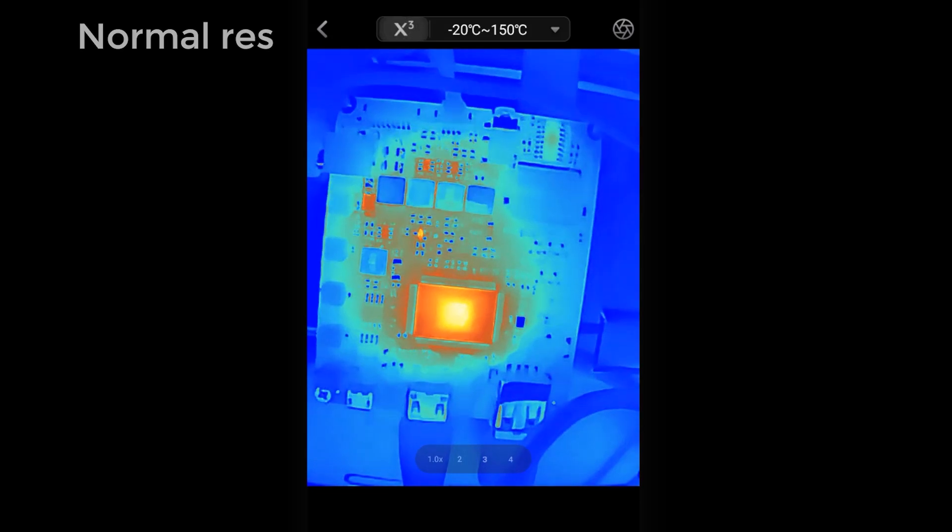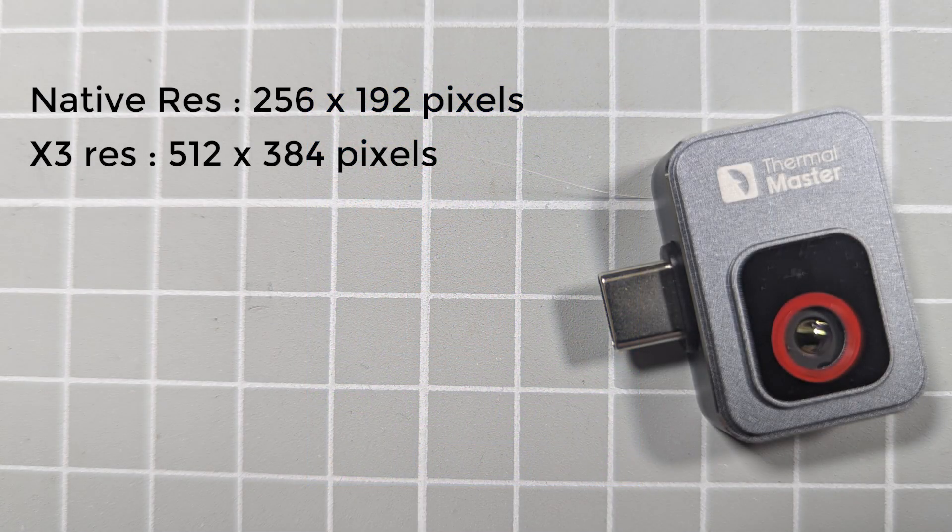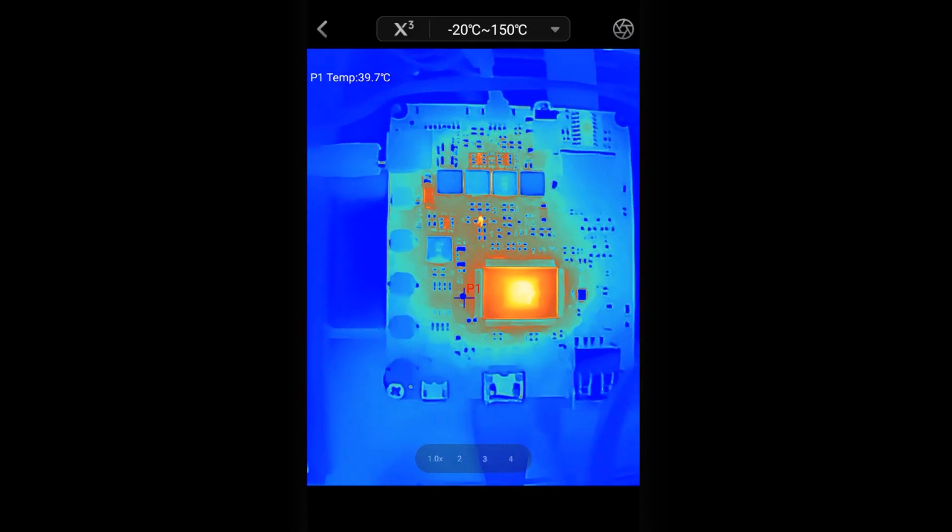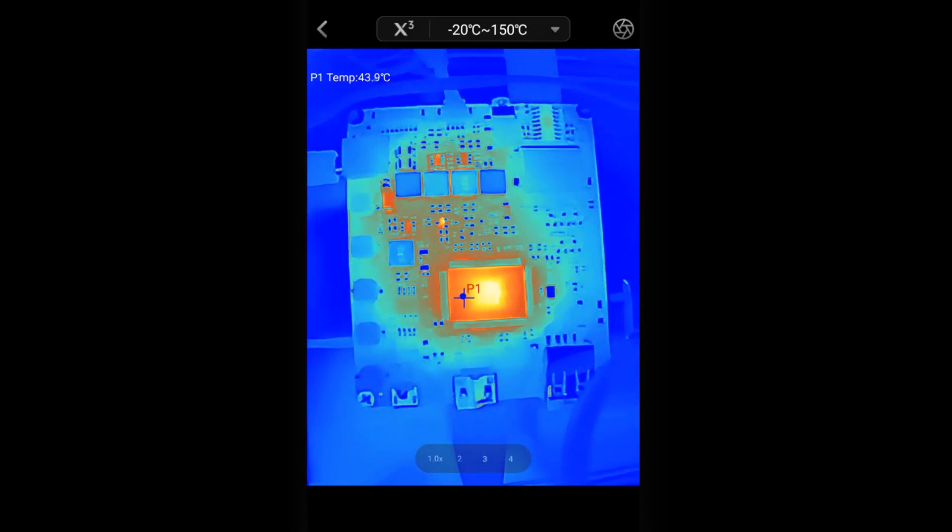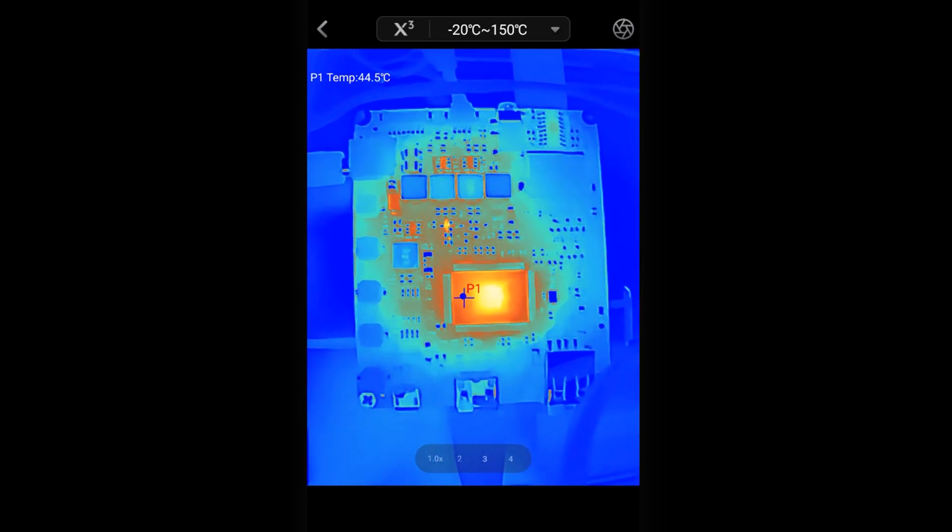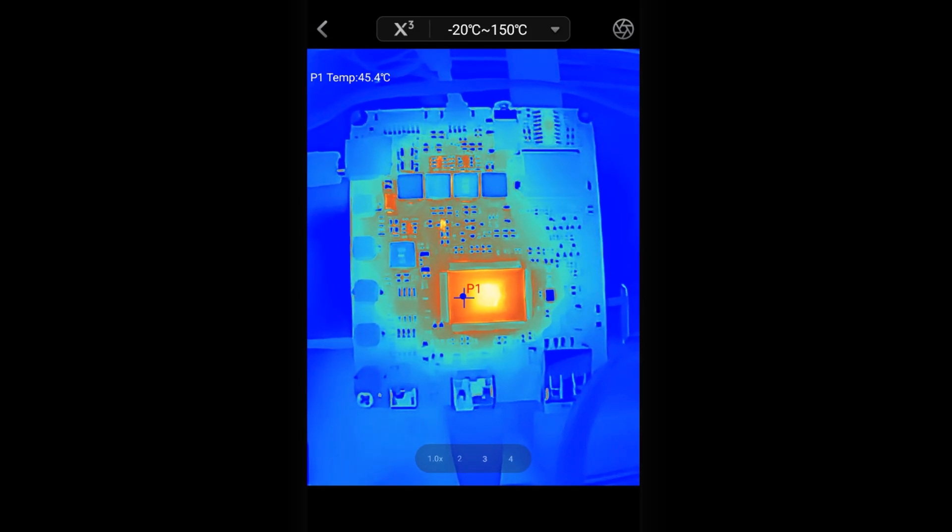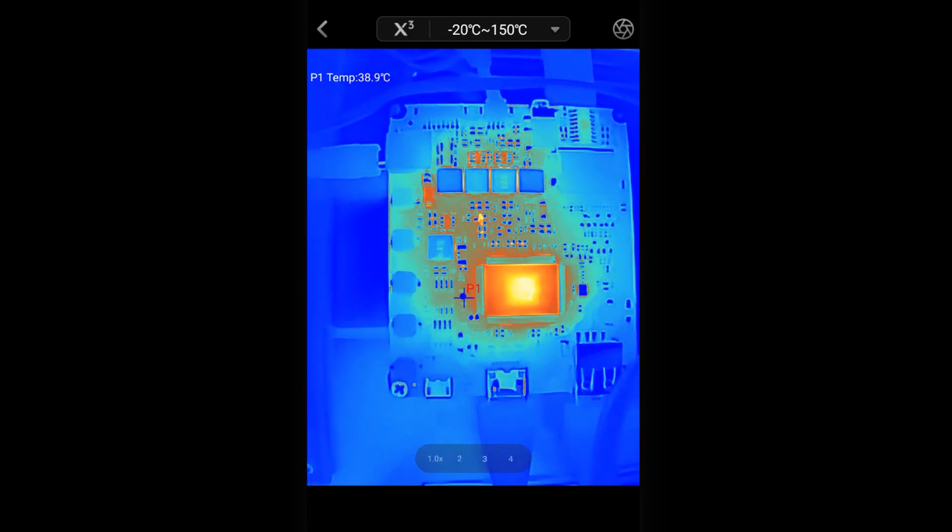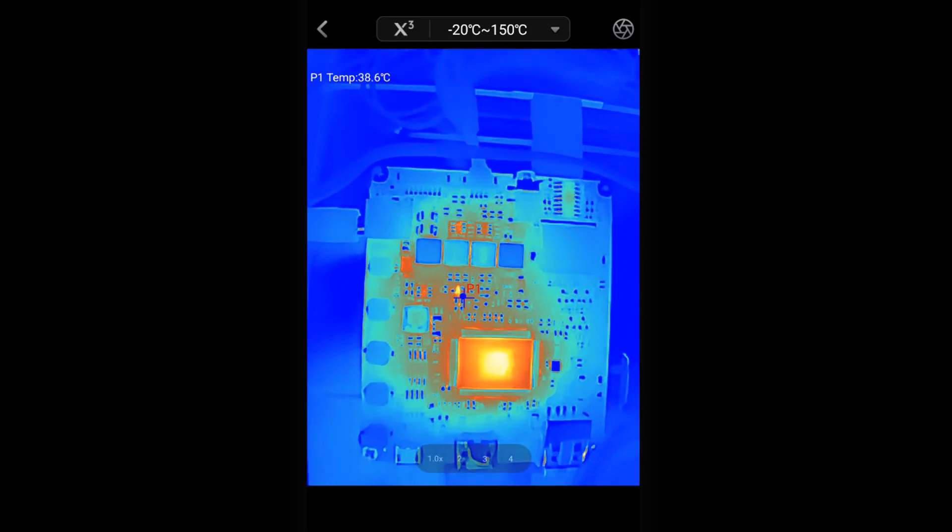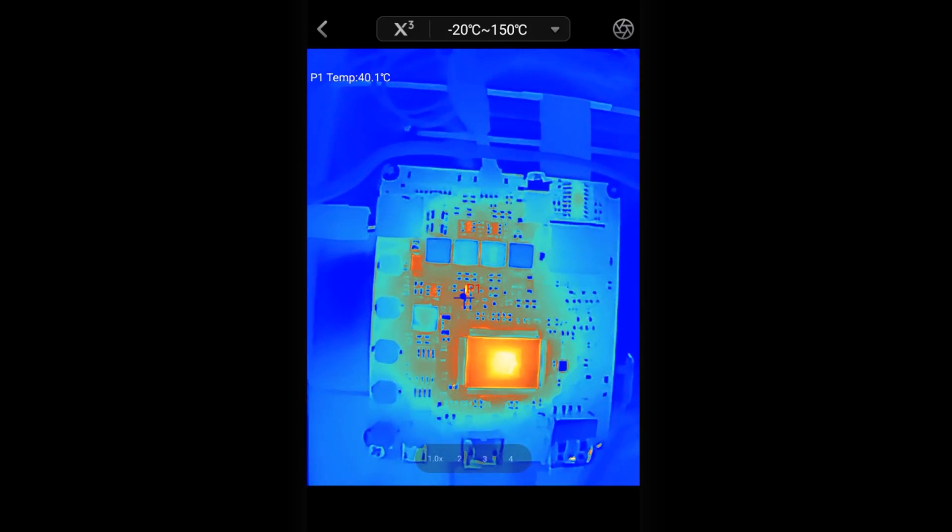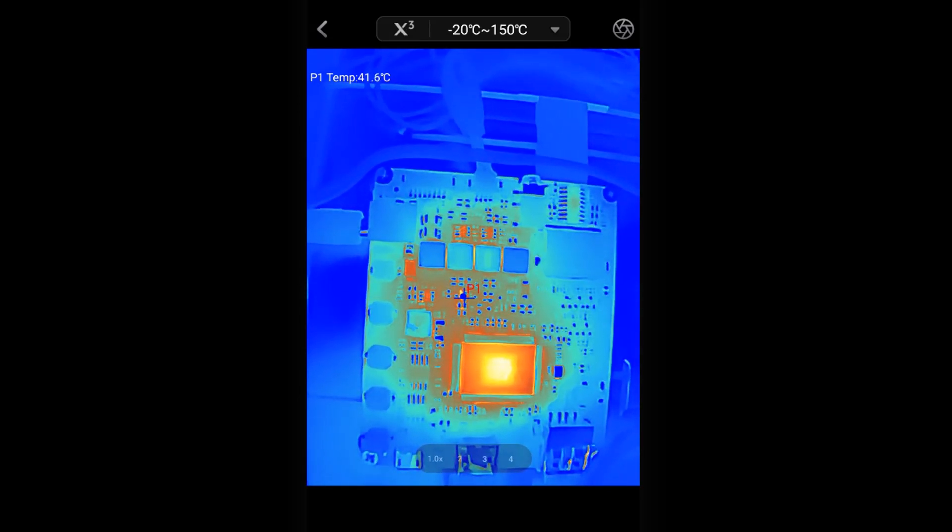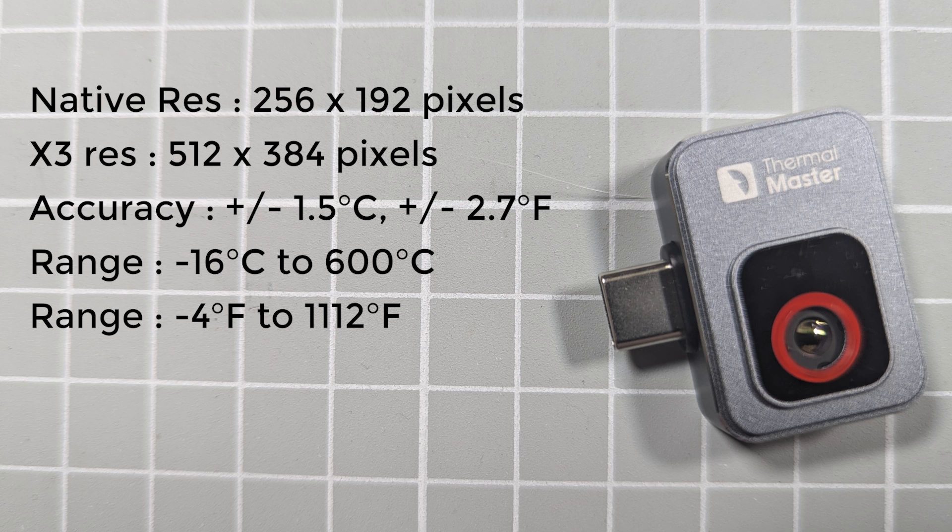Secondly, we need to consider the accuracy of our camera. The P2 states that the temperature accuracy is plus or minus 1.5 degrees centigrade over a temperature range of minus 16 degrees centigrade to 600 degrees centigrade. In Fahrenheit, that's an accuracy of plus or minus 2.7 Fahrenheit, with a temperature range of minus 4 Fahrenheit up to 1112 Fahrenheit. This is a pretty good accuracy rating and puts the P2 into what you'd call a quality device bracket.